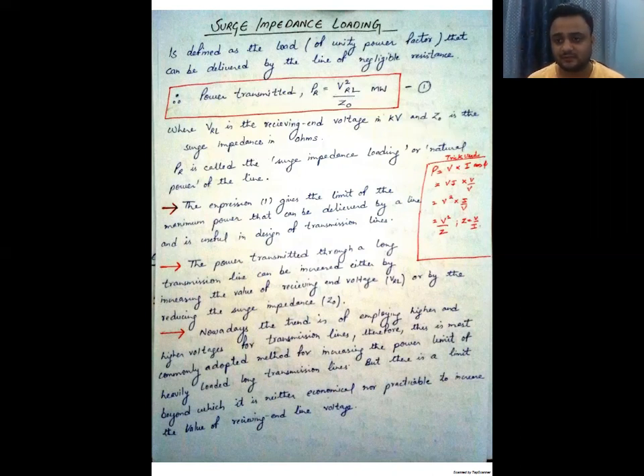We had learned in the previous video two formulas for surge impedance of a transmission line. The first formula is the square root of the ratio of the line impedance to the shunt admittance, known as surge impedance for a particular loss-free transmission line.